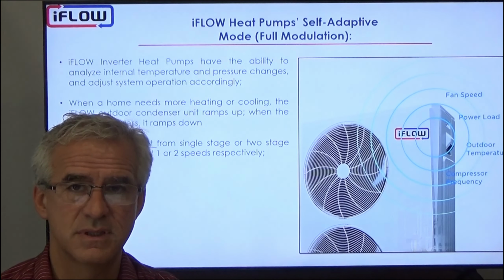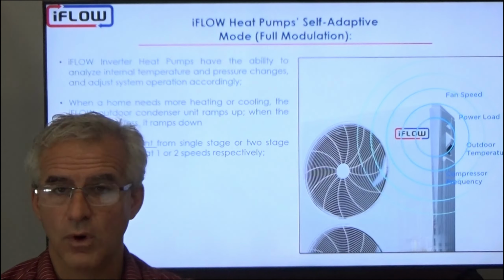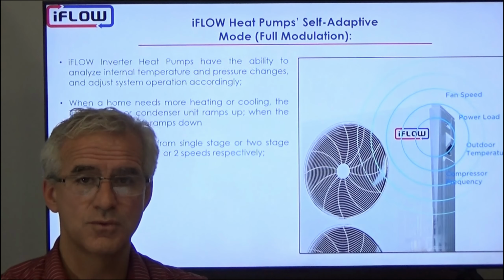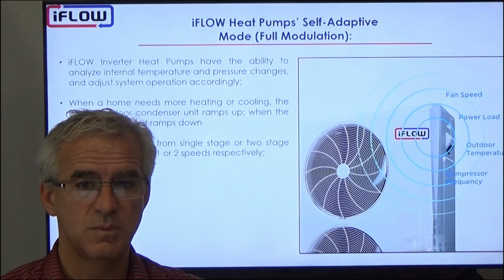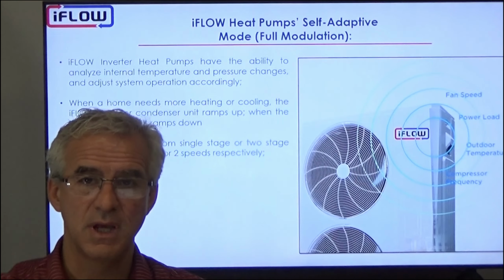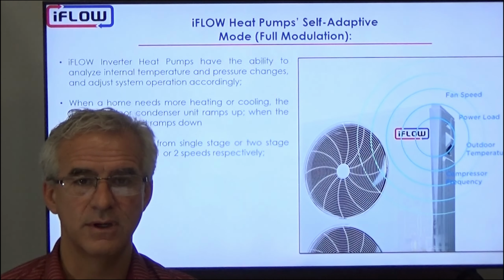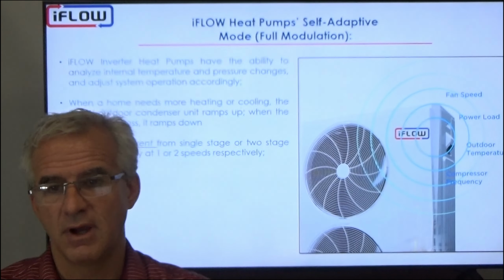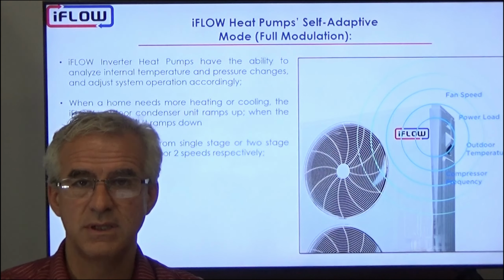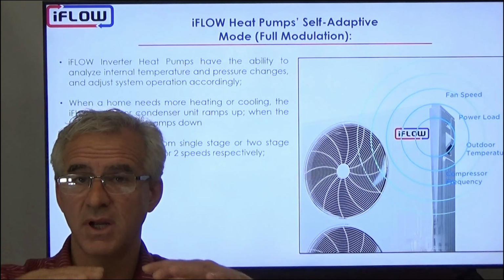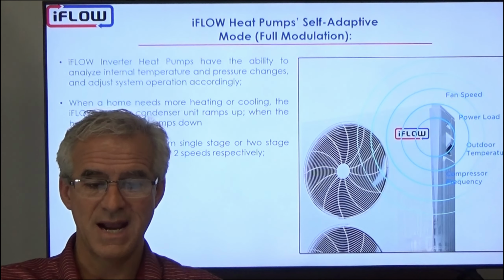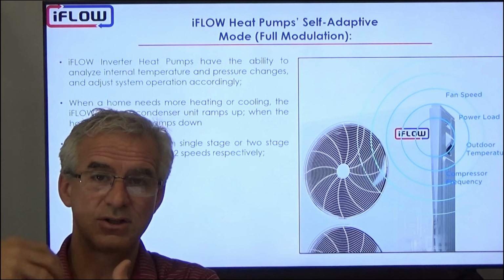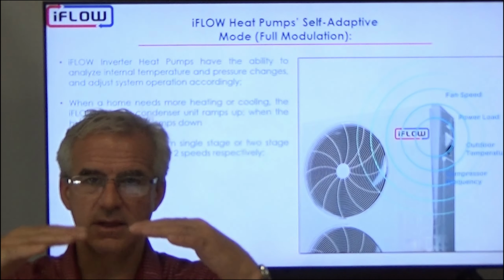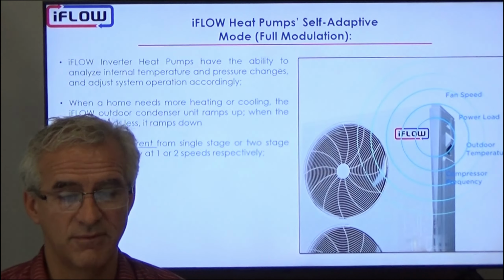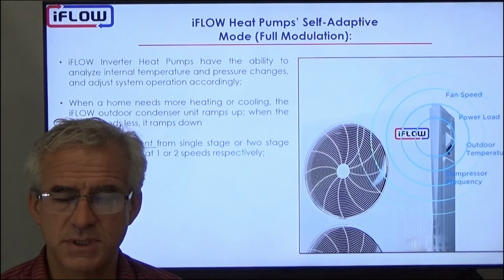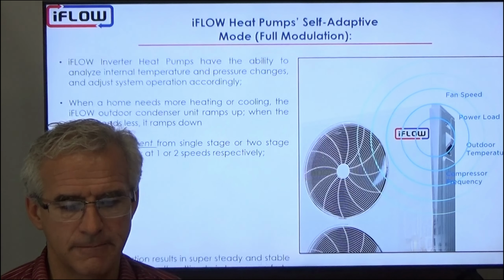And this is very different from a single stage or two-stage unit, where they run at 1 or 2 speeds respectively. If I have a single stage unit, it's just running at 1 stage. So if I need 3 tons or 36,000 BTUs, it's just going to try and run at that level. It's not going to be able to adjust to seasonality or different temperatures within the house. If it's a cold day, I might need 36,000 BTUs in the morning, but if I get some solar gain during the day, I might need to back that off a bit. If I continue adding the 36,000 BTUs in addition to the solar gain, I could overheat that space. So I need the ability to ramp up and down, and that's what the modulation gives us. Again, very different from single stage or two-stage units in that way.